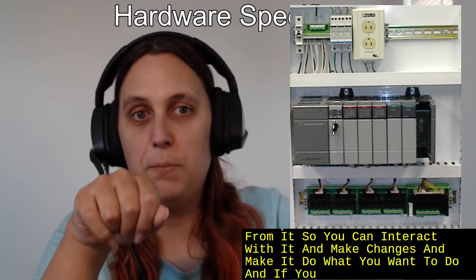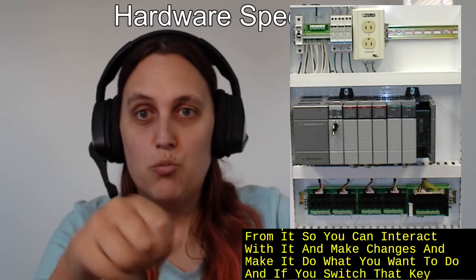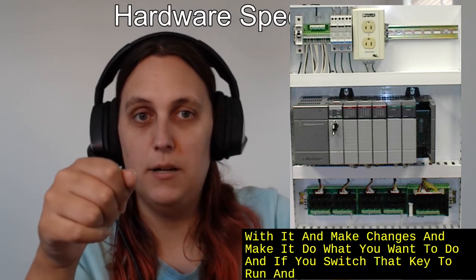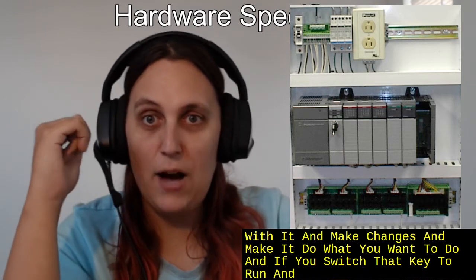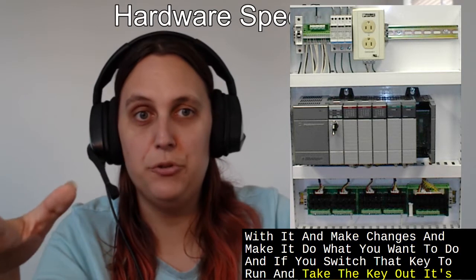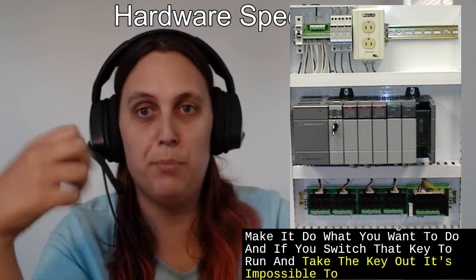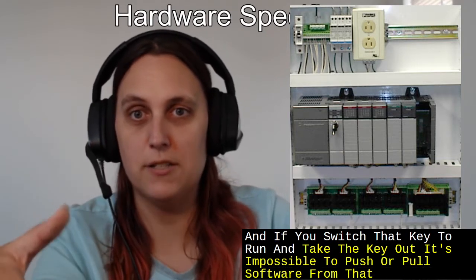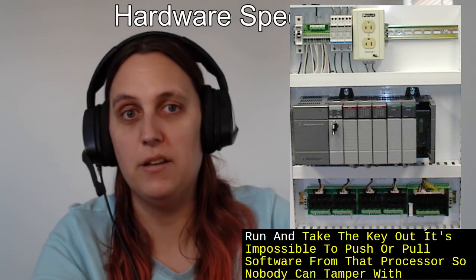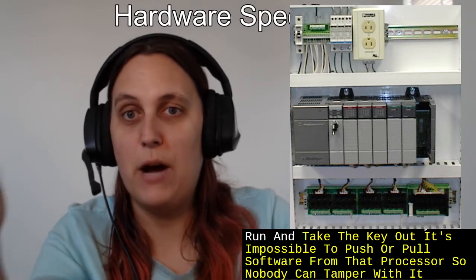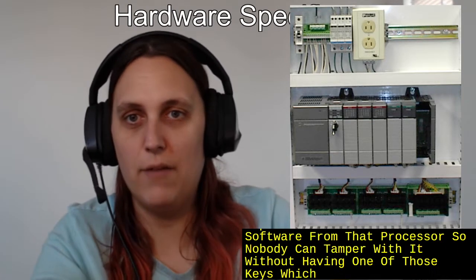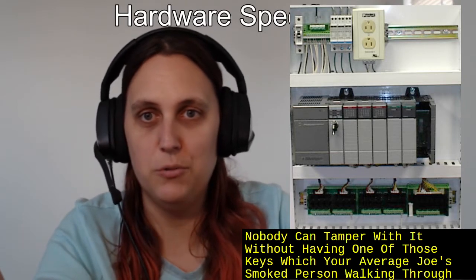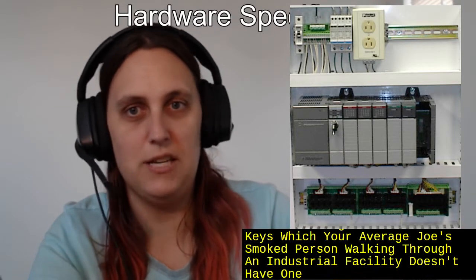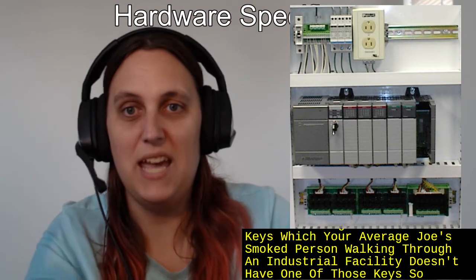And if you switch that key to run and take the key out, it's impossible to push or pull software from that processor. So nobody can tamper with it without having one of those keys, which your average Joe Schmo walking through an industrial facility doesn't have. So they can't mess with it.